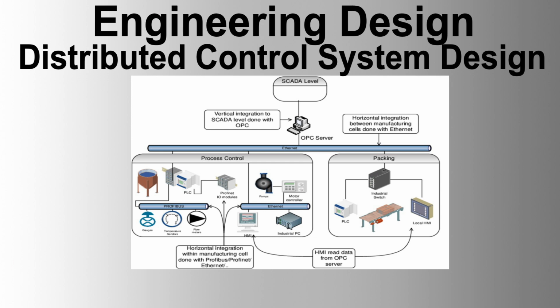6. System interfaces. The DCS must interface with existing consoles, cabinets, fire and gas detection systems, compressor unit control systems, power generation systems, package systems, switchgear interfaces, field instrumentation, pump and motor monitoring, telecom systems, and other specified systems. All I/O must be repeated to the DCS via dual redundant serial links with alarm initiation for link faults. The DCS must fully control remote systems with the same functionality as local panels, capable of initiating startup, maintenance overrides, and equipment trips over serial links.